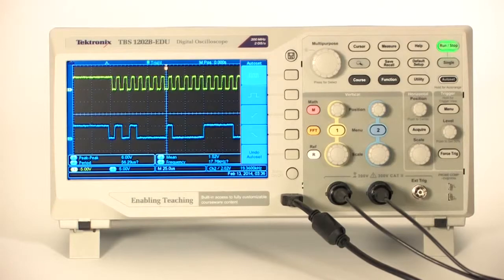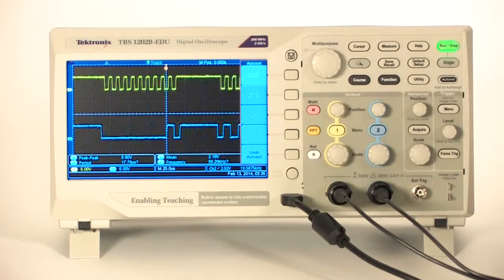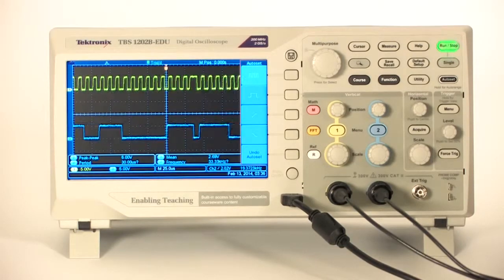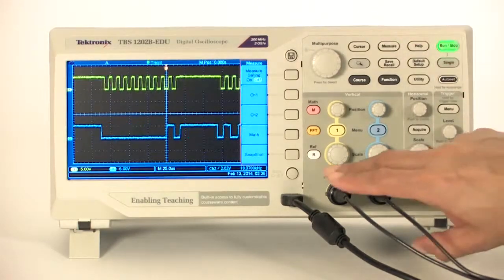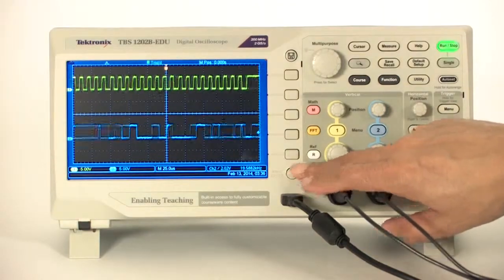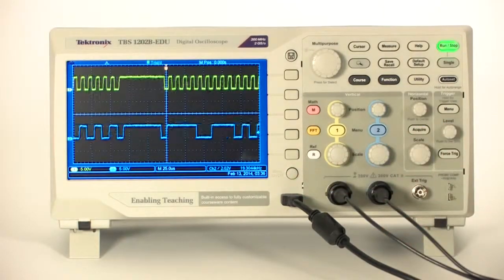Often, digital data comes in packets. Simple edge triggering won't allow you to pick out the packets. You can use pulse width triggering to capture them. Let's take a look at some I2C information.